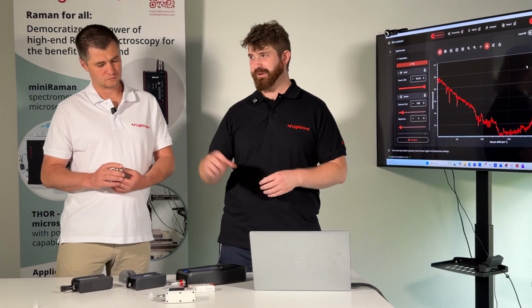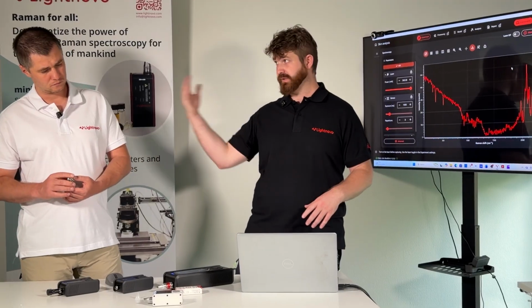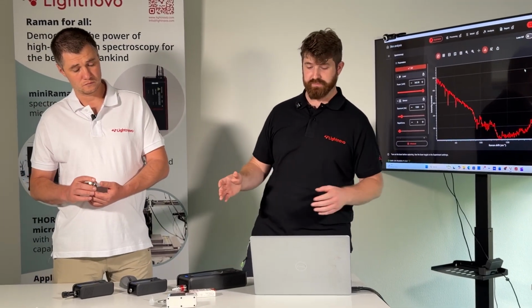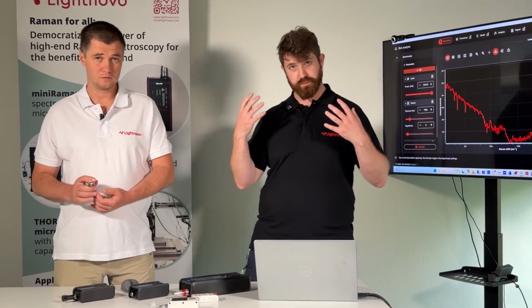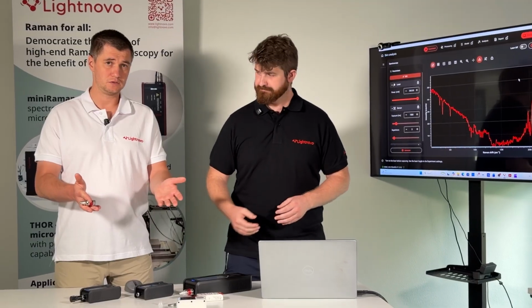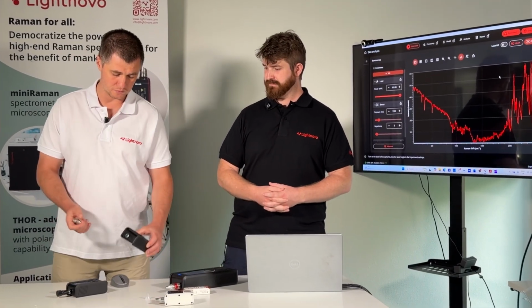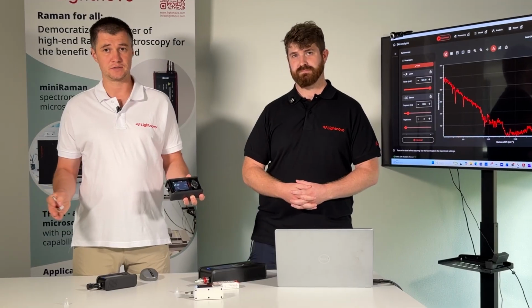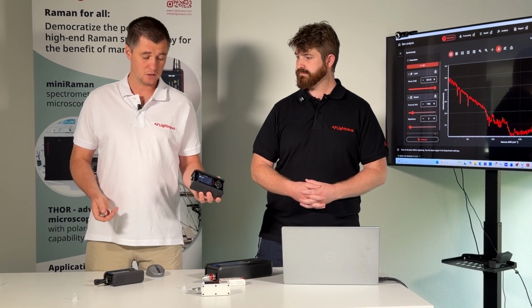Anyone else in the office, the lab, even us standing right next to the devices are perfectly eye safe, which is why we don't need to be wearing laser goggles. So when there is no probe on the device, the beam is parallel, and that is class 3B, where you need safety glasses and you are not allowed to point it at other people or your eyes.